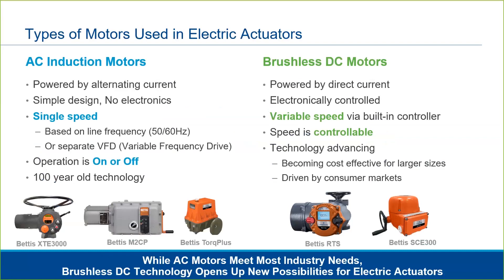AC induction motors are powered by alternating current. They operate at one fixed speed based on the frequency of the AC current being provided to them. So the same motor powered by 60 hertz current would operate at a faster speed than if it were powered by 50 hertz. In some cases, speed could be varied with an external variable frequency drive, which serves to vary the current being supplied to the motor.